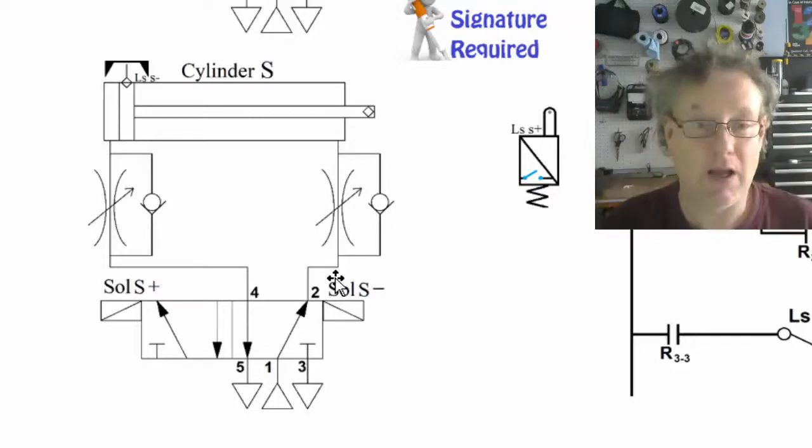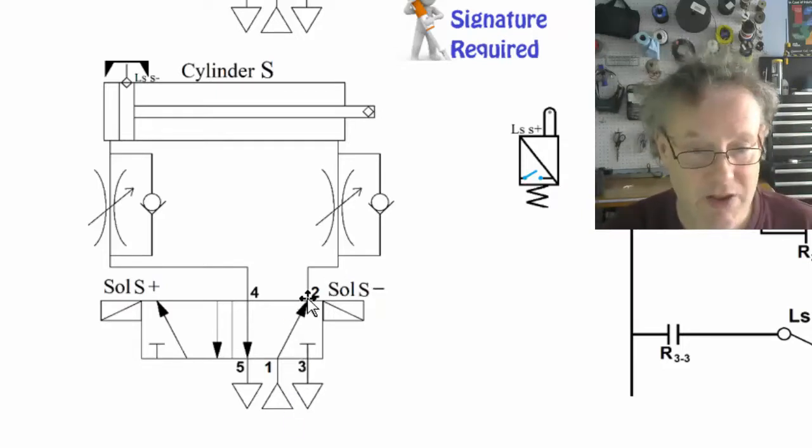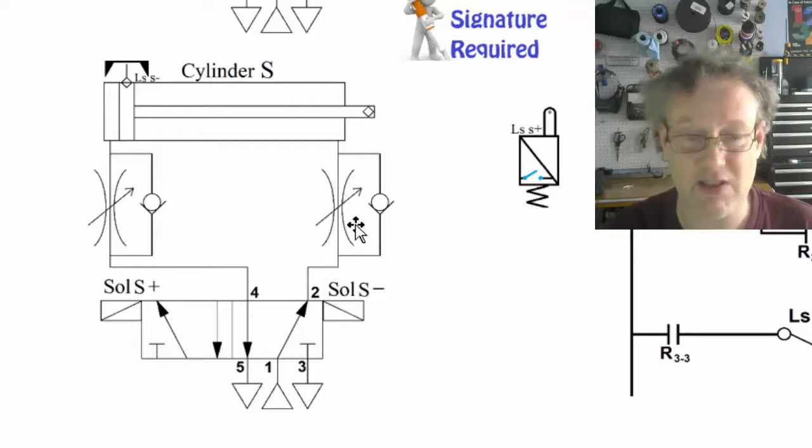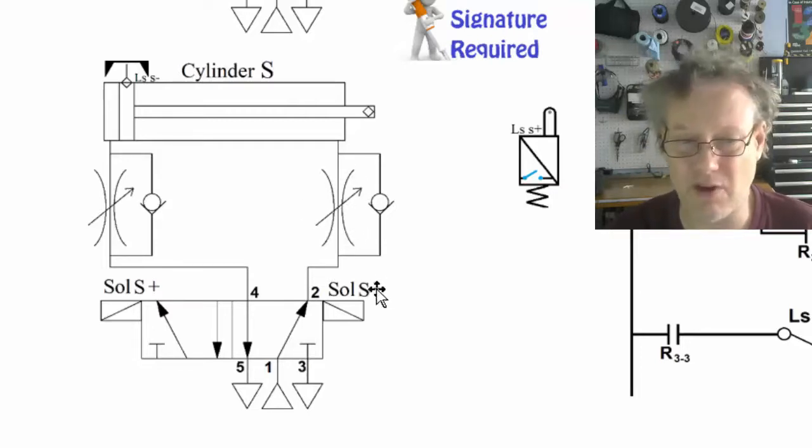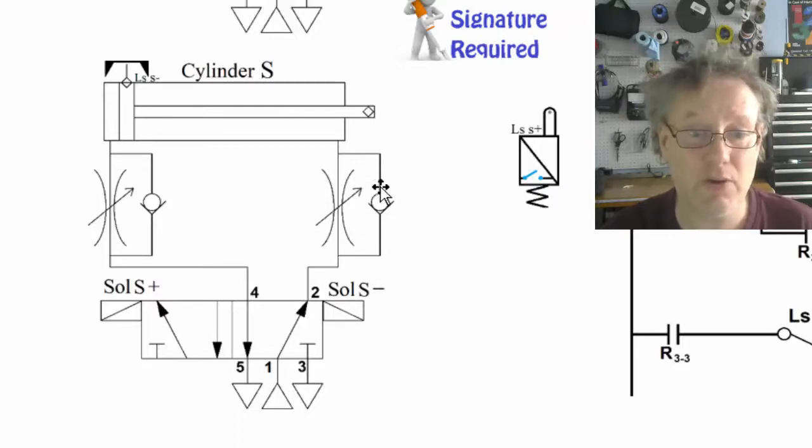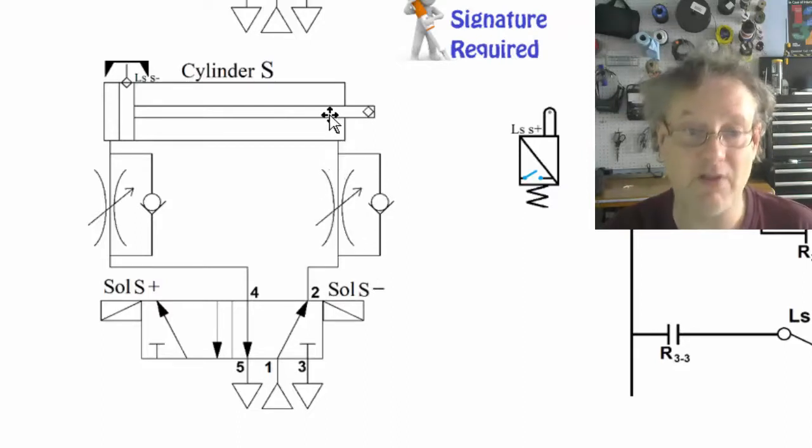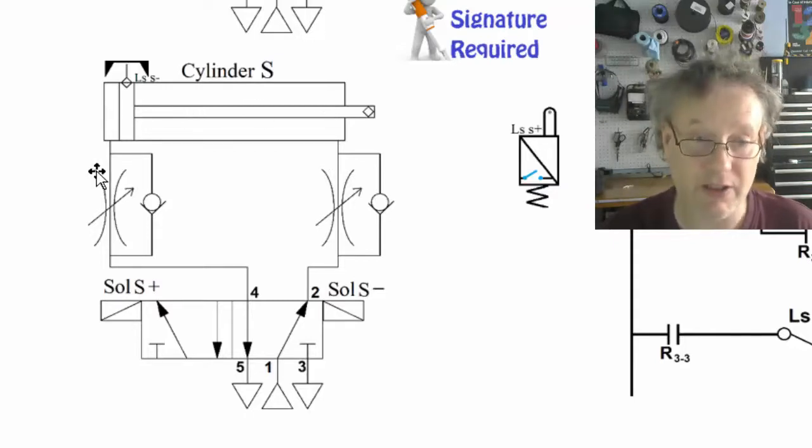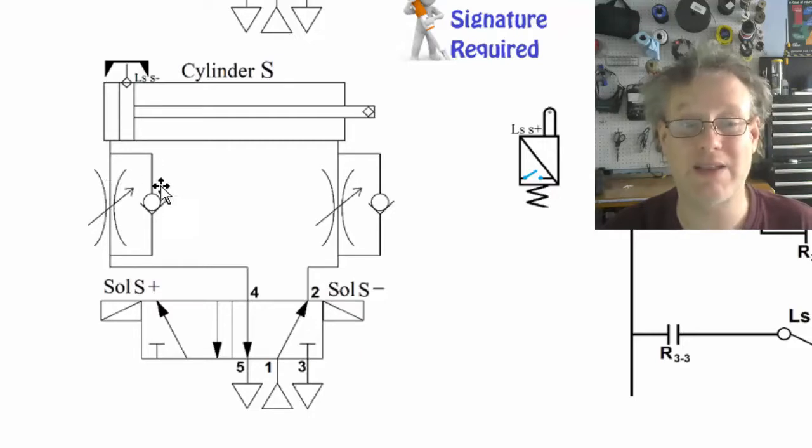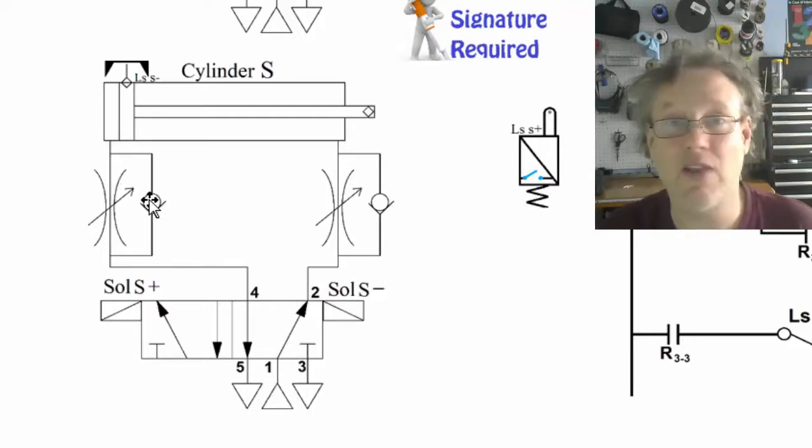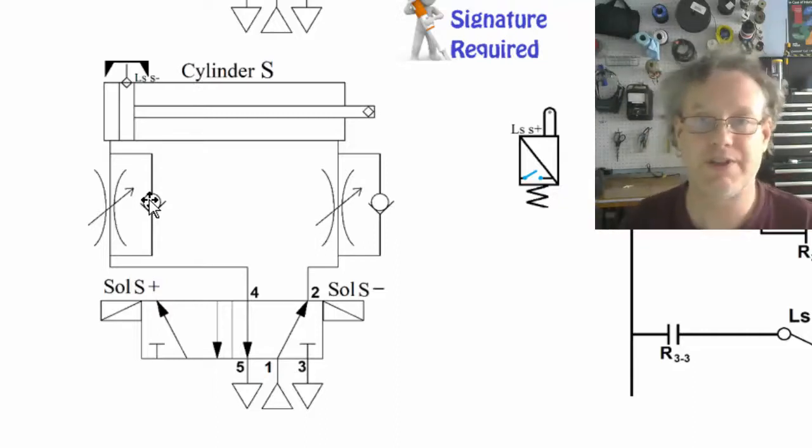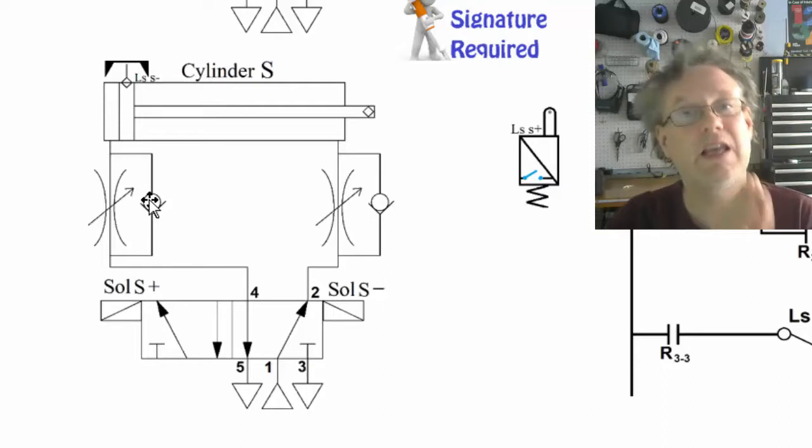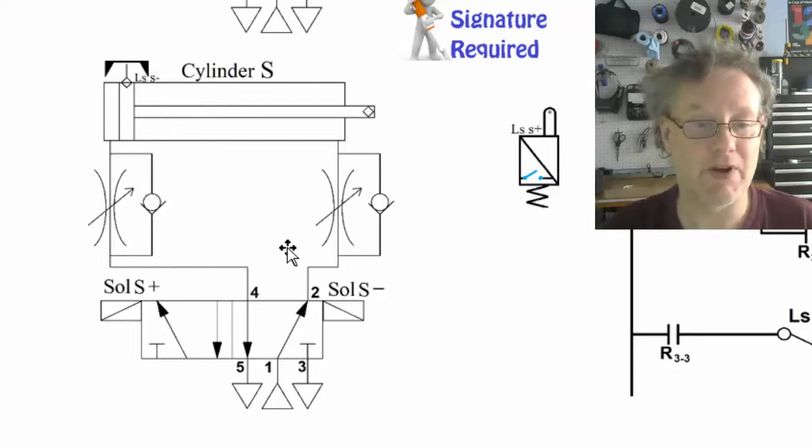So now let's take a look at the option of the retraction. So the air is going to come up through here. It's going to get to here. It's going to see this throttle valve. It's going to be like, dude, I don't want to go through this throttle valve. Oh, look, there's a check valve here that can be wide open. I'm just going to go through the check valve, bypass this throttle valve. I'm going to go in here. I'm going to retract the cylinder and the air coming out of the cylinder will be forced to go through this throttle valve because when it sees this check valve, it says, oh, I can't go that way. So now we're throttling the air coming out, which is again, metering out. I'm controlling the speed in extension and retraction.